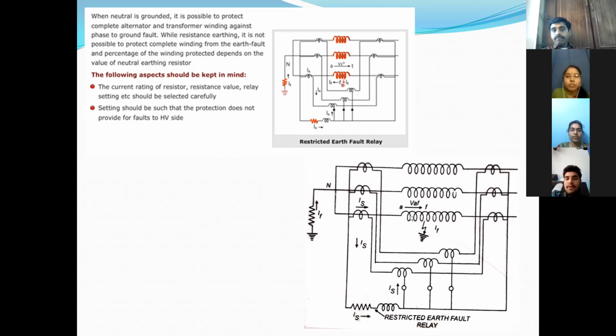Here you see, when a fault occurs in one of the lines here, the fault current flows to the ground, and from the same ground it goes to this resistance, that means a resistance connected from neutral to ground, and it goes in this direction. That means this is the path in which the fault current flows. Why is this resistance generally connected? To limit the fault current.